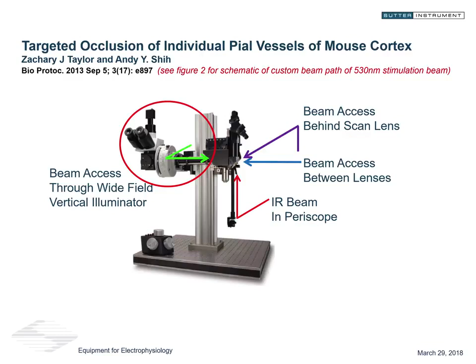Okay. So light sources. I think in the example in the beginning, I showed a little LED that was on the side of the microscope. But there's actually all kinds of light sources, as most of you know, that can be used for imaging. And in this case, we see two of our workhorses here. These are xenon lamp-based light sources. So xenon light puts out a wide, very broad spectrum, very powerful light across a broad spectrum. And our Lambda LS is sort of the workhorse xenon light source for microscopy, whereas the Lambda DG4 has some exciting features built in so that it can do very high-speed switching of the wavelengths of light that it's using and sending to the microscope.